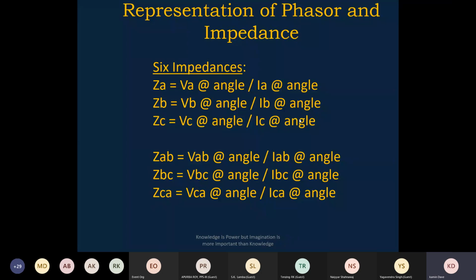I see there are two things: either the fault has to be covered from the EHV side, or else you can cover the bus duct fault, because the algorithm has to work this way. Or else you can use zone 1 for this and zone 2 for this in the backup impedance. So first you understand the fault phenomena and then the relay algorithm. According to the fault phenomena we calculate the real impedance recorded by the relay, seen through the waveform, and then we try to understand the relay algorithm, and then we fit the settings into the relay.